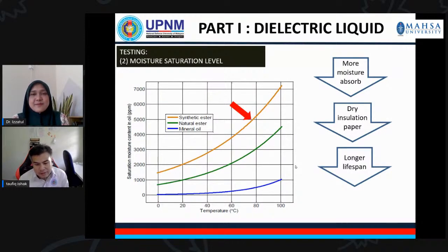Based on this study, as you can see from the graph, in terms of moisture saturation level, the natural ester can absorb more water than mineral oil, which is a good thing, in which it can prevent free water from forming. It means that when you have the capability to absorb more moisture inside the oil without exceeding the solubility point, then free water will not form in that particular oil. So this is a very good thing.